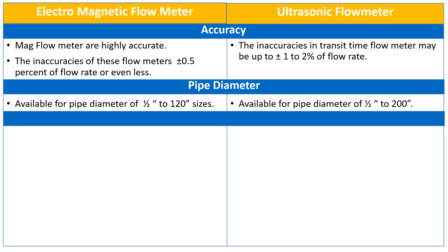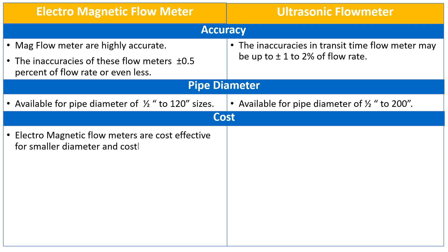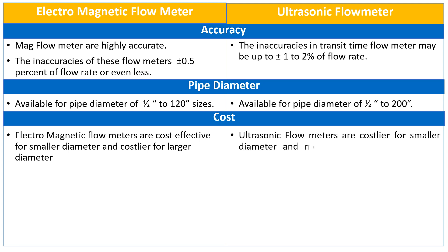Finally, we will discuss the cost of both flow meters. The electromagnetic flow meters are cost effective for smaller diameter pipes and costlier for larger diameter pipes, while the ultrasonic flow meters are costlier for smaller diameter pipes and more cost effective for larger diameter pipes.